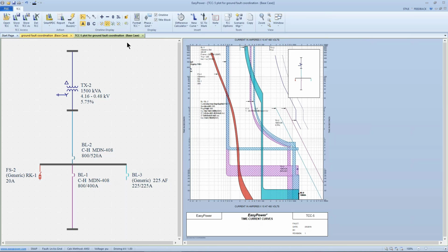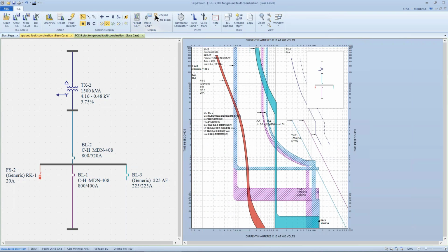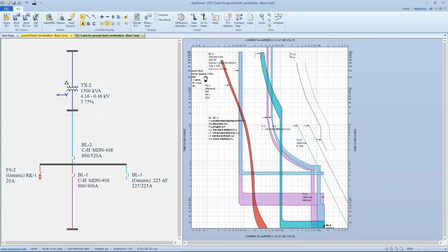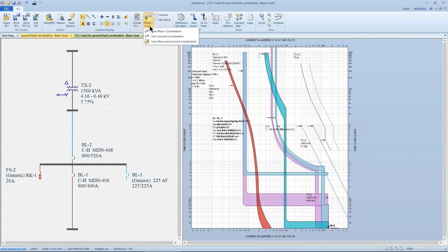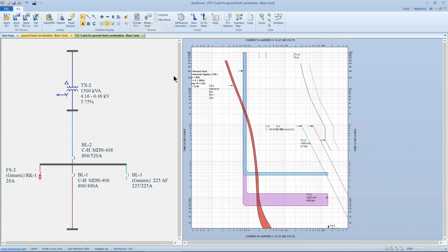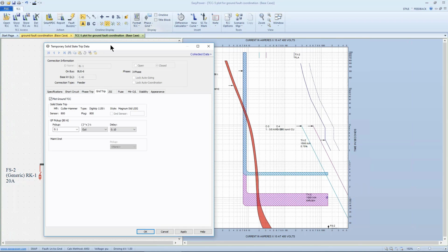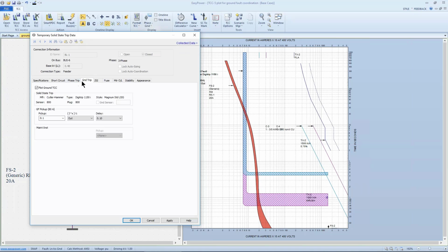And again, we want to primarily look at ground fault. So it's showing us the phase trip curves as well. Let's take those off the display by selecting just ground coordination. And what we see here is that we have two similar breakers with these Cutler Hammer devices, and consequently they're not going to coordinate unless we modify one of the settings. So if we go in and look at this farthest downstream ground fault trip, we see that its setup is at the lowest point.